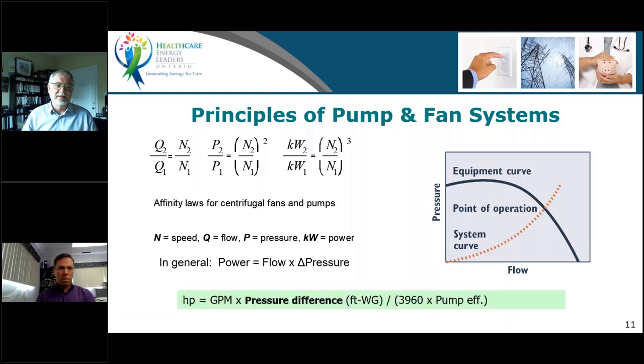In a pump and fan system, they're basically the same principles. We're going to talk about pumps today, but the same principles apply to fans ultimately. On the little picture on the right-hand side, many of you have seen this before. It's the performance curve that relates where that pump wants to operate, relating pressure to flow. So it wants to operate somewhere on this line. And then the system that the pump is forcing fluid into responds by putting up a resistance to that flow. The system wants to operate on this dotted red or orange line here. And where these two cross is where the pump and the system decide they're going to operate. They come to an agreement, and that has implications for the efficiency and the amount of power the motor has to provide as well.